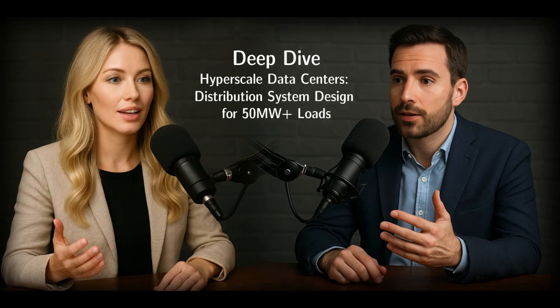And the other big power quality villain, harmonics. Data centers are infamous for generating them. What's the scale of the problem and how do you fight it? They are indeed harmonic factories, mostly due to all the switch mode power supplies in the servers and the variable frequency drives often used in cooling systems. You can see harmonic currents that are, say, 15 to 20% of the fundamental frequency for the fifth harmonic, maybe 10 to 15% for the seventh. Add it all up, and the total harmonic distortion, or THD, coming from the facility before filtering can easily be 20 or 30%. And that distortion causes problems for the utility grid, right?